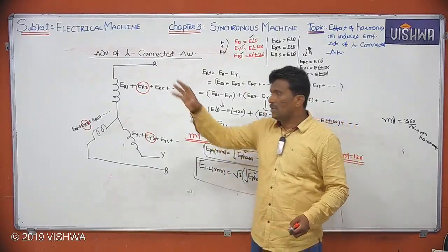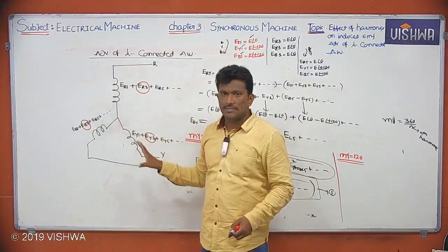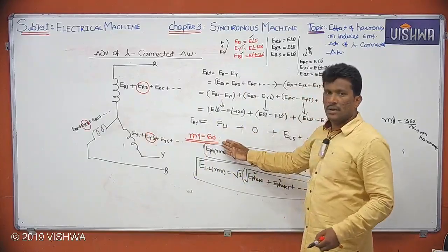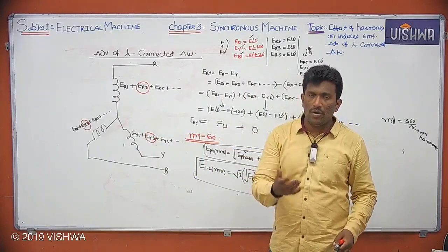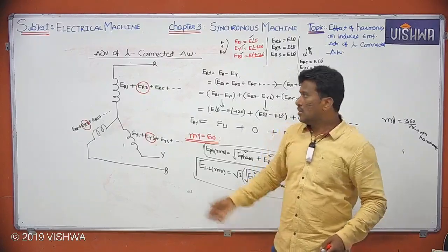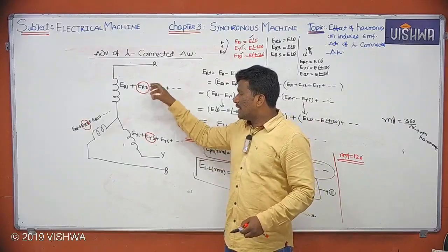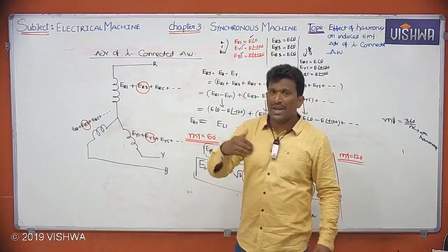For example, in a generating station there is an alternator which is star connected. Generally, we keep mγ equals how much? 60 degrees. Why? I told you, phase EMF will be more, output power will be more, kVA rating will be more. So you may get a doubt: sir, because of mγ 60 you are having triplen harmonic voltages in the phase. Let it be, because what about the line?